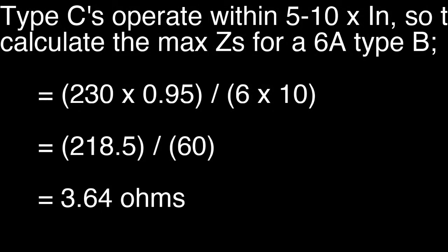So if we take a look, we've got an example calculation for a type B, and then we can compare it with an example calculation, same rating, 6 amp, but for a type C. Let's do the type B first. Just want to remind people that it is the instantaneous tripping that we're talking about. We're not talking about short circuit.